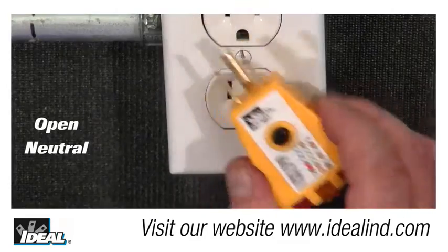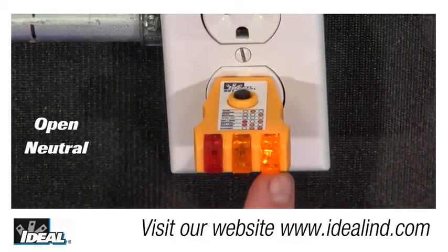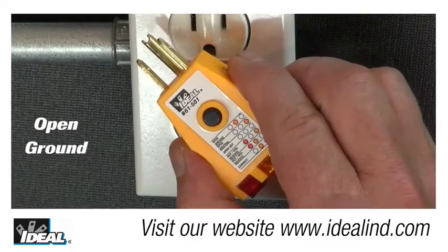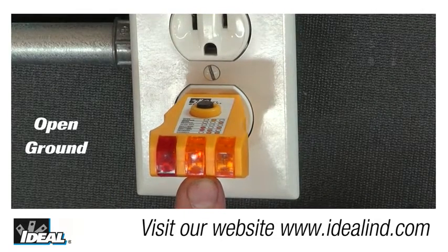at all. And if you have an open neutral, only the far right bulb will light up, indicating a condition that probably needs to be addressed. And for an open ground, only the center bulb is lit, and the other 2 will remain unlit.